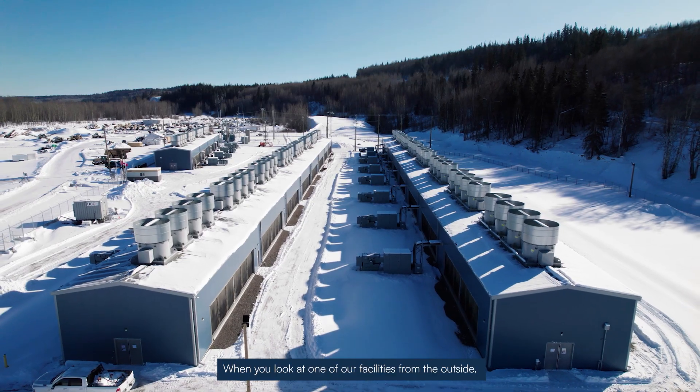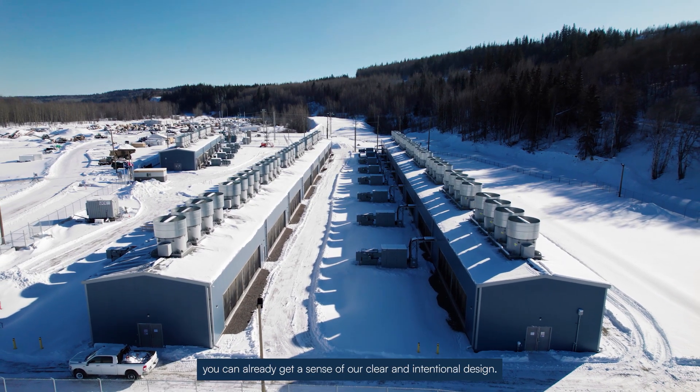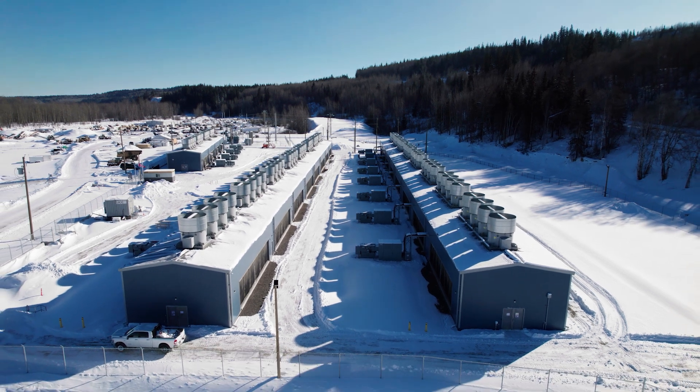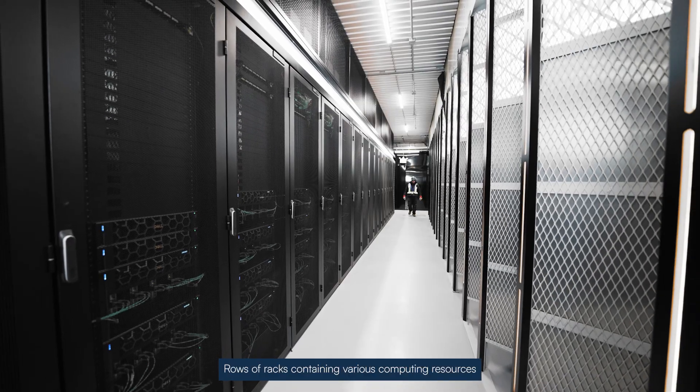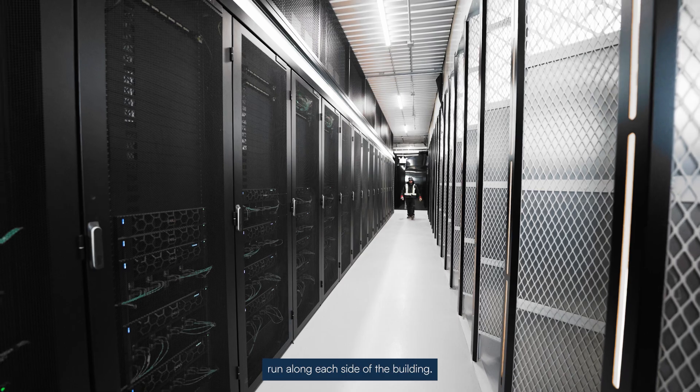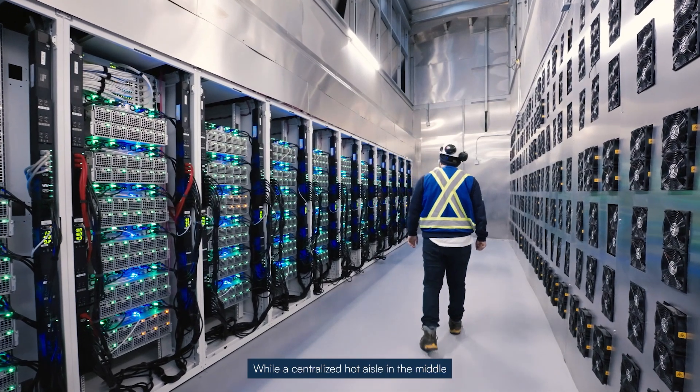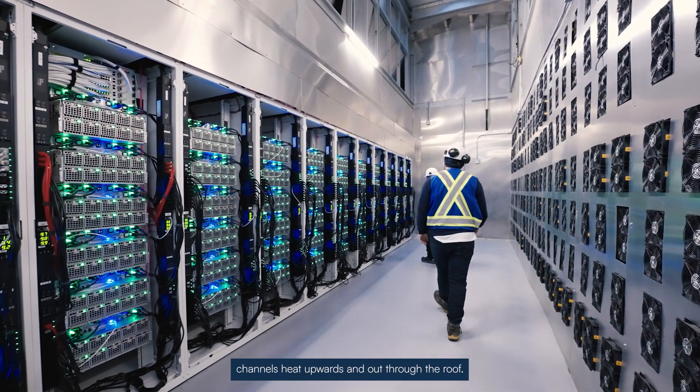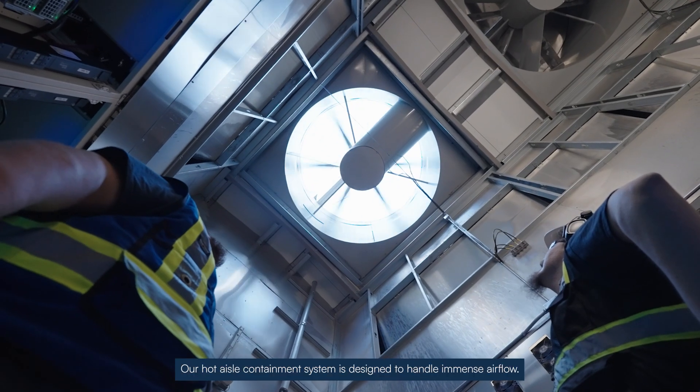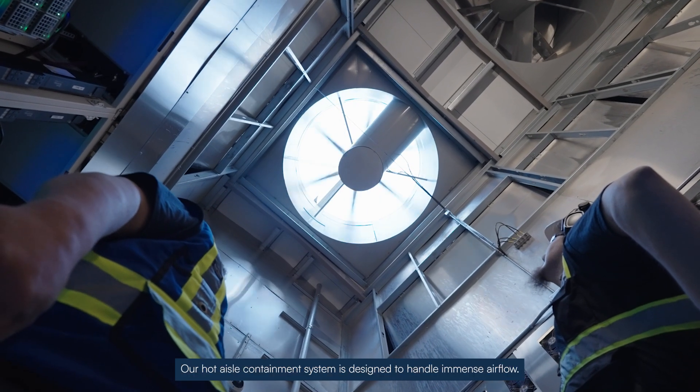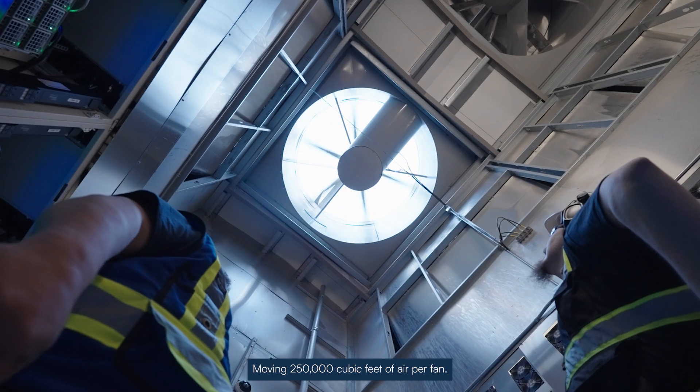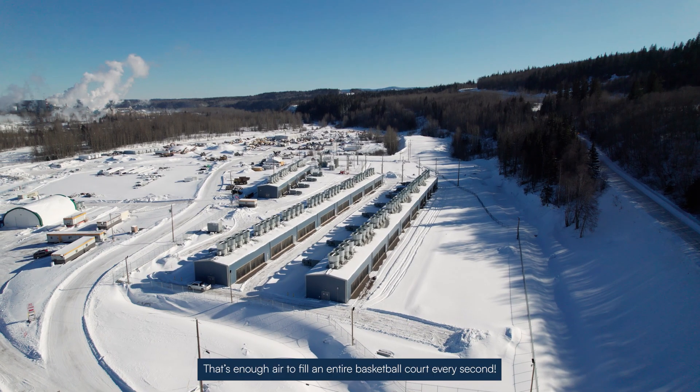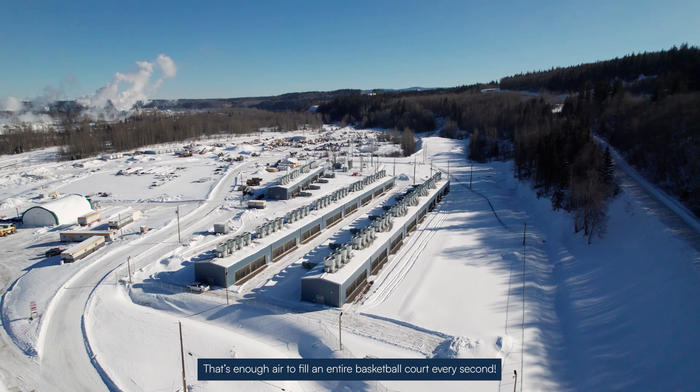When you look at one of our facilities from the outside, you can already get a sense of our clear and intentional design. Rows of racks containing various computing resources run along each side of the building, while a centralized hot aisle in the middle channels heat upwards and out through the roof. Our hot aisle containment system is designed to handle immense airflow, moving 250,000 cubic feet of air per fan. That's enough air to fill an entire basketball court every second.